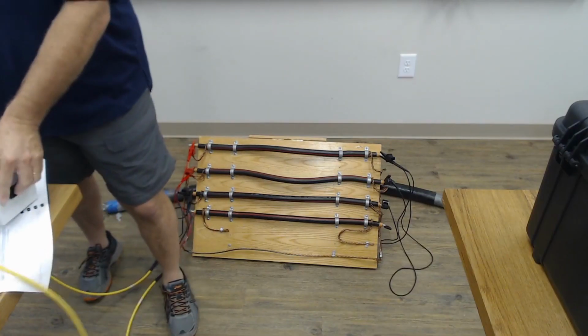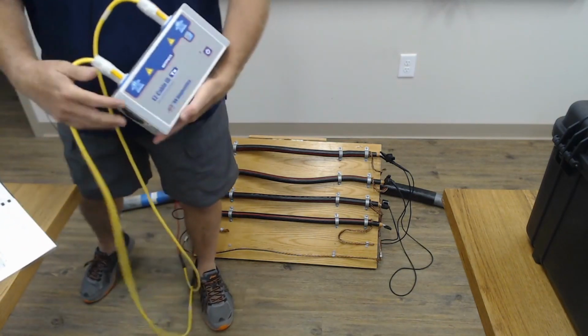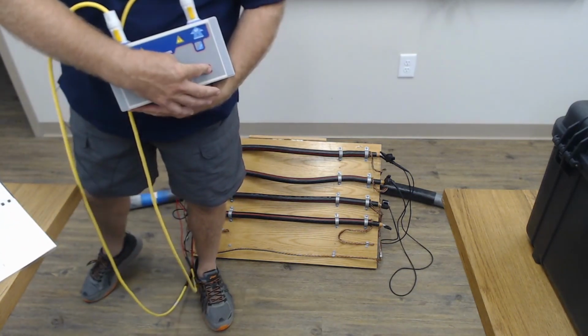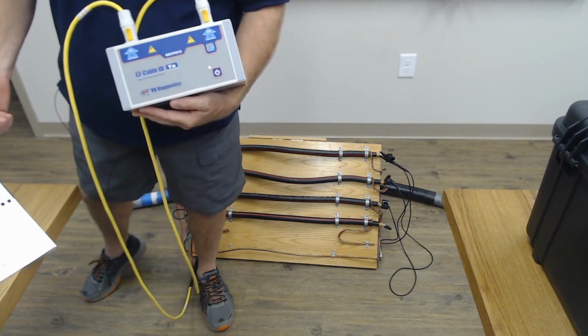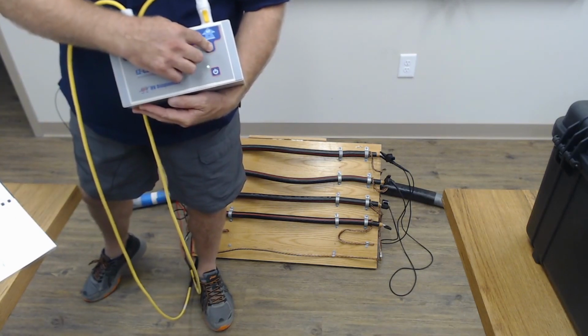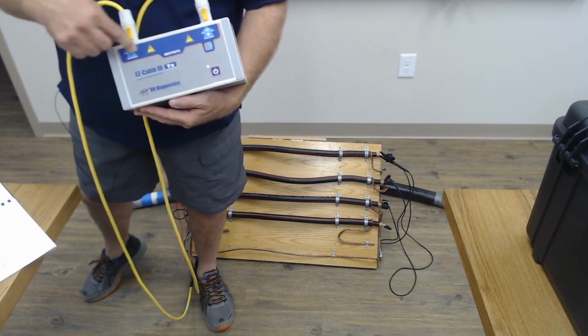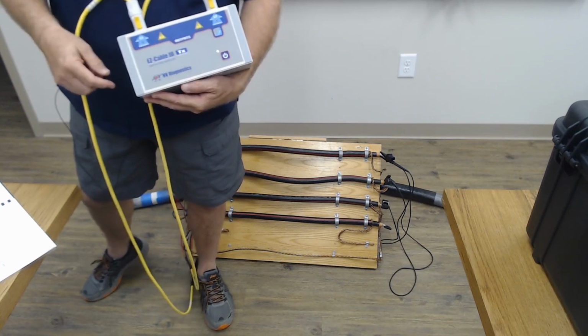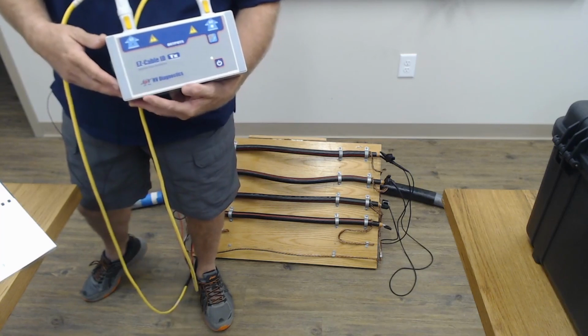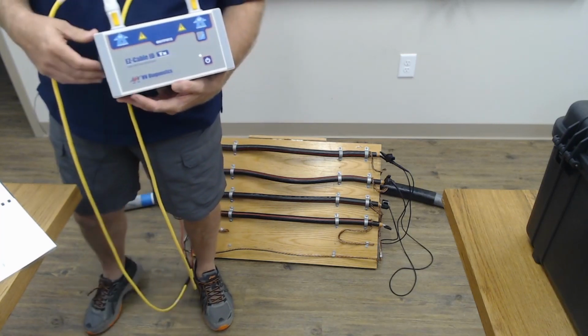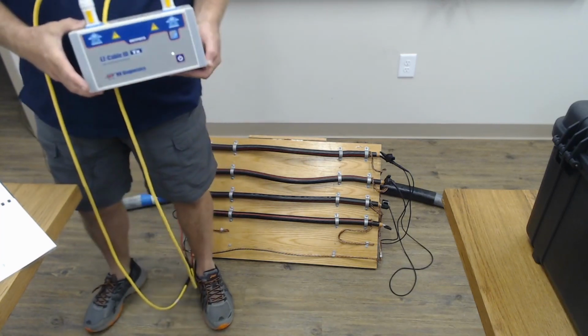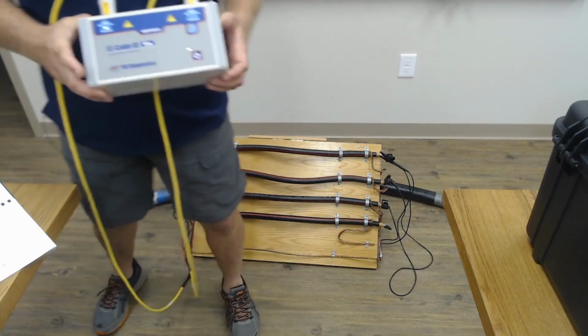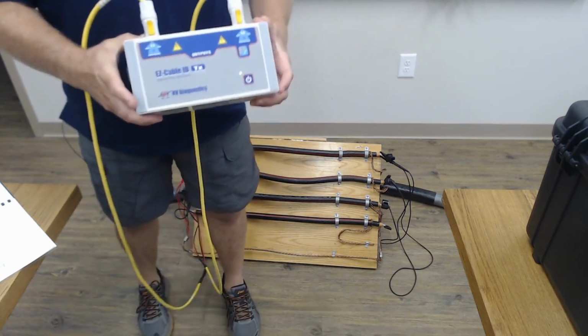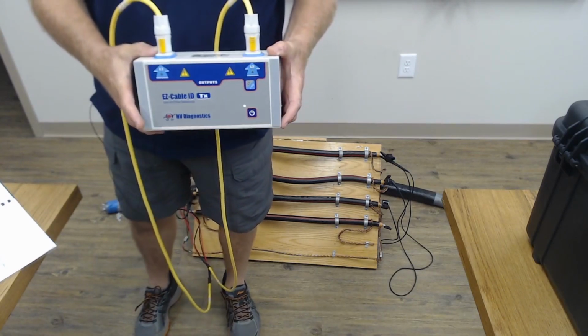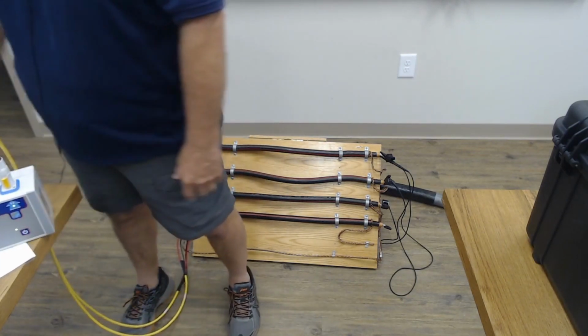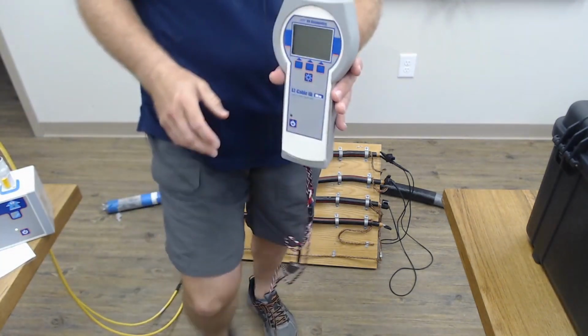So with that, we can turn on the transmitter. Here's the transmitter over here. I'm going to turn it on. Because we're doing a three-phase ID, I want to make sure we're on three-phase. And I also want to make sure that we have the green lights on. If we didn't happen to have a ground on the far end, or sorry, the C phase connected to the A and B phase, we would not get a green light here. So that's important that we get green lights when we do that test. So everything's good to go. There we go.